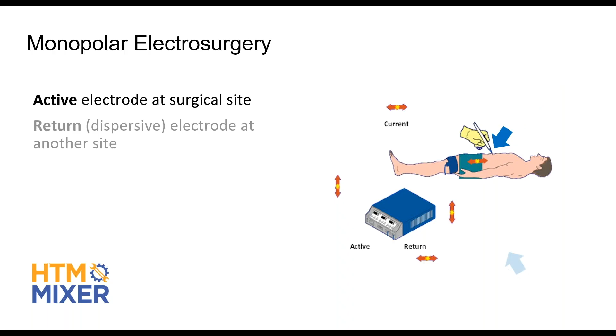It's called a dispersive electrode because you can see in the picture there, if you put this down on here, we have a high concentration of electrical current there because it's pointed. So you have a high concentration here. This one is also called an electrode, a return electrode. Active electrode, return electrode. What's the difference between these two? They're both electrodes.